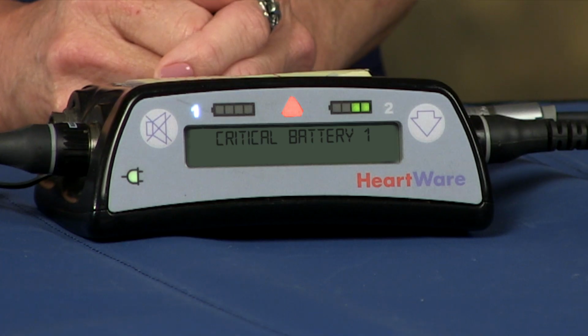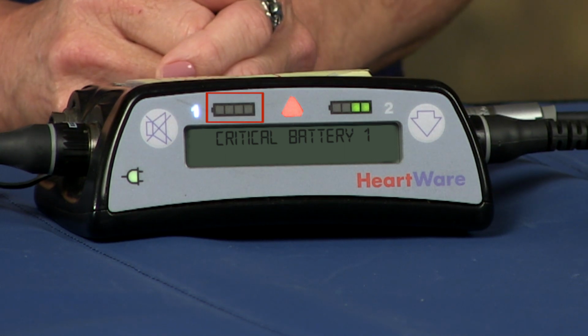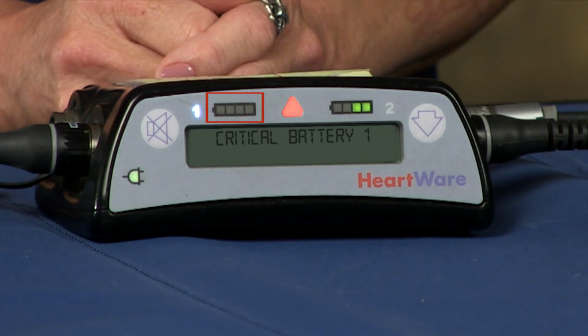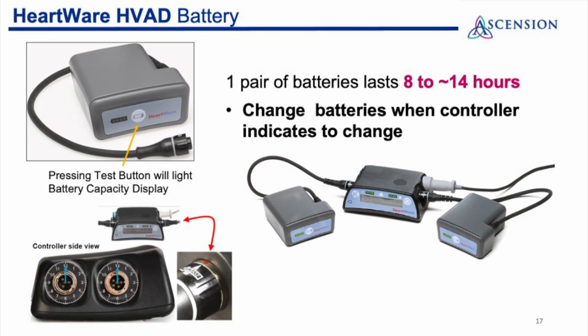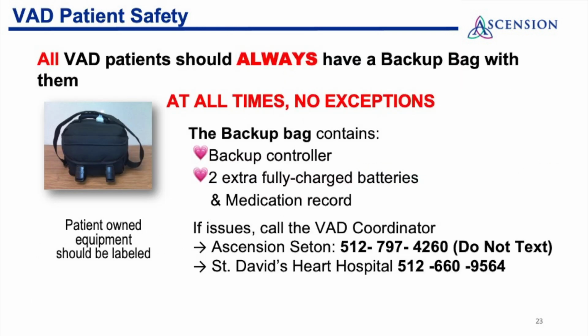When the AC power cable is disconnected to attach a battery, the controller will auto-flip to the already connected battery. If the patient is already on battery power and a battery alarm occurs, the controller will tell you which battery to change first, battery 1 or battery 2. Just follow the controller's instructions. HeartWare HVAD batteries also have a fuel gauge. Each bar represents 25% power. These patients also need to have their backup equipment with them at all times. This includes an extra HVAD controller and 2 fully charged batteries.